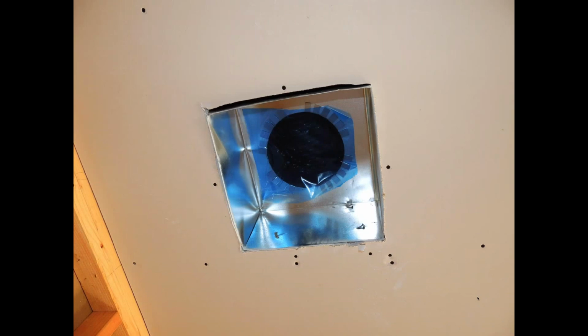In other words, here, this might appear that this home has less duct leakage than it would when it's finished, because they put the air seal over the perimeter of the inside where the duct interfaces the boot. But if you pull that off, you can see that that's not air sealed. You can see a lot of air leaks around the perimeter of this boot. And so this home may look good in terms of its testing, but unless the testing is done right by qualified people who follow ResNet protocols, chances are you're not going to see the performance you're hoping for.